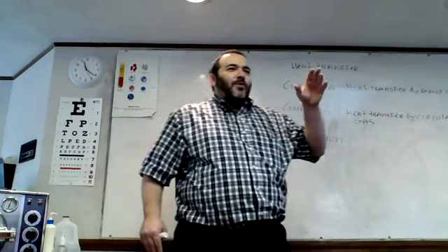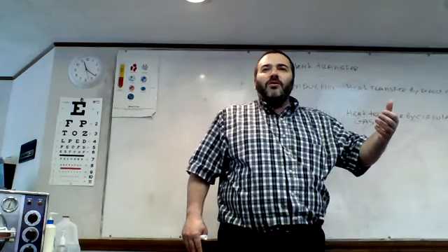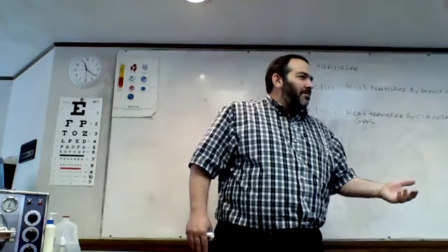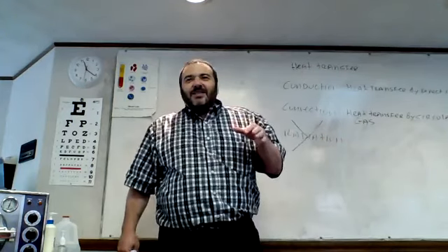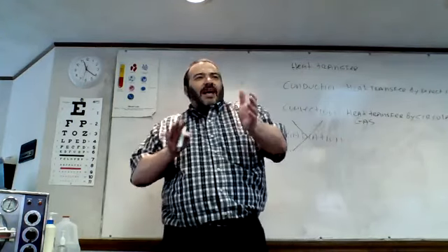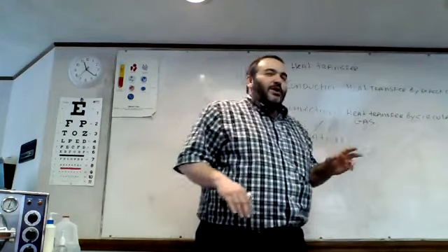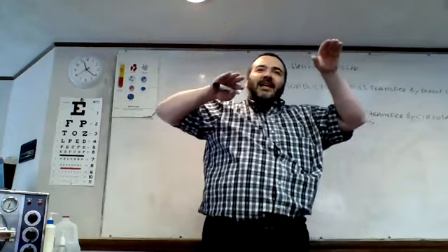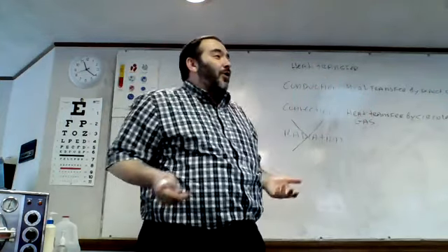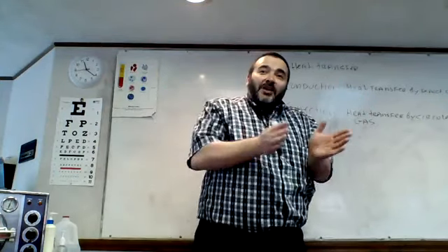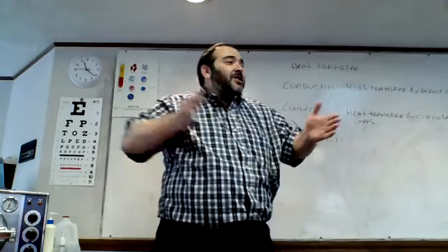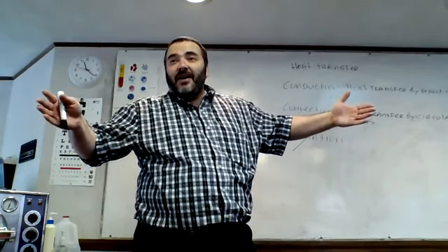So one way to remember: where water won't flow, steam won't go. Kind of like that, right? If you're putting things too tightly in there and the water cannot flow freely around it, the steam is not going to go. So things need to be laid out neatly with enough space for things to flow around them. Okay? So packages cannot touch one another. Packages cannot touch the sides of the chamber, right?